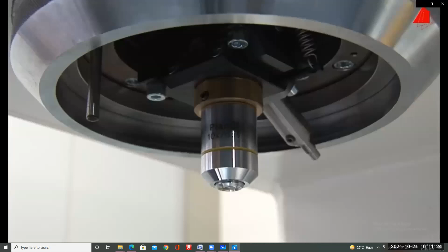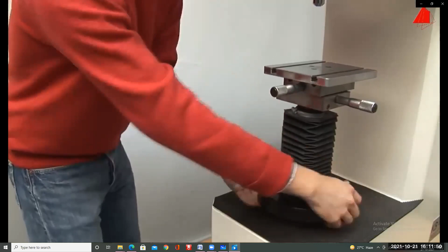So with the control panel, a microscope lens with a digital camera and an indenter. These are connected to each other and rotate towards the required position. It's also possible to select and exchange the indenter, so different methods of hardness testing can be used on the same testing machine. The support table can be adjusted in place, so the test piece can be positioned at the correct distance to the lens and the indenter.